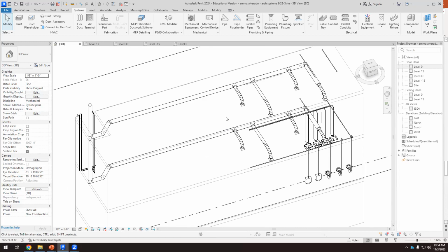If we supply air, we can consider that part of the air in this room can go through the building into a different room. We don't want the air in the restroom to go to different rooms. So that's why in the restroom, we only have the exhaust. We only exhaust, and then the supply diffusers, part of the supply air will enter the restroom, and then it's extracted and we get rid of it.